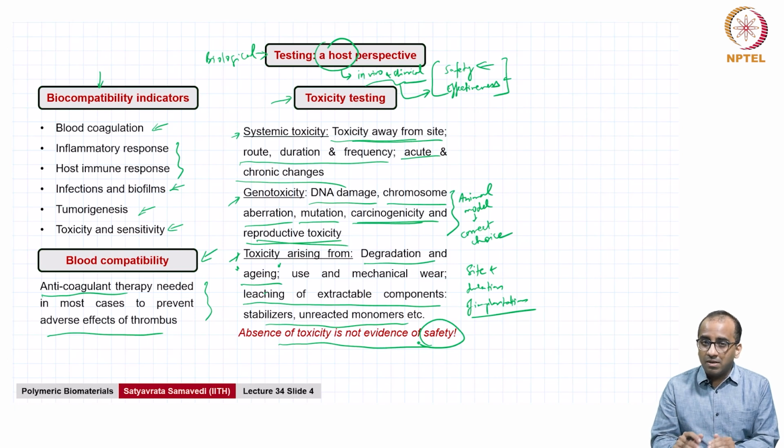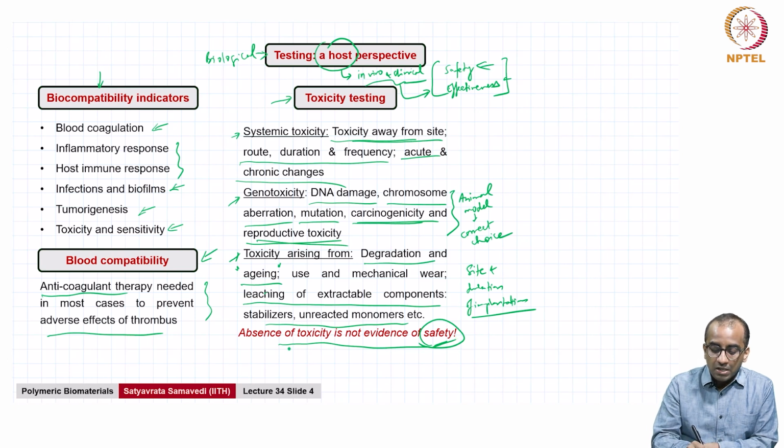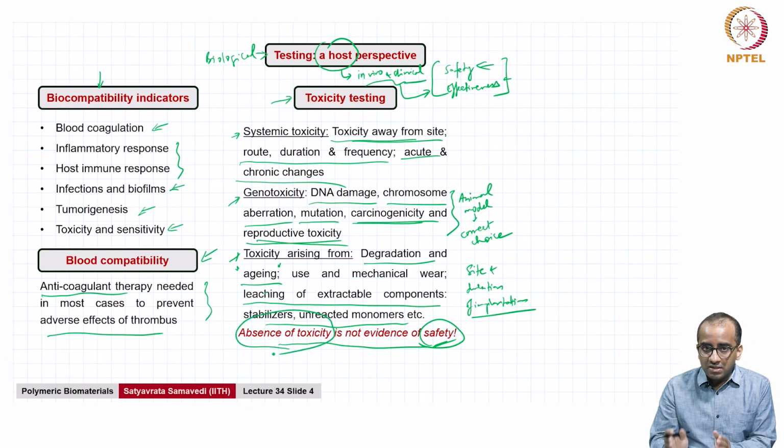Sure, toxicity is one important aspect of safety, but the kind of toxicity testing that is done here is not absolutely conclusive of the safety of the material or the device itself, because it cannot account for all the scenarios. Although that continually keeps getting reviewed and the standards keep getting updated, it's very difficult to conduct testing where all scenarios are accounted for. So there is always one caveat to be kept in mind: absence of toxicity in these testing studies, which is good, is not complete evidence of safety of the medical device.